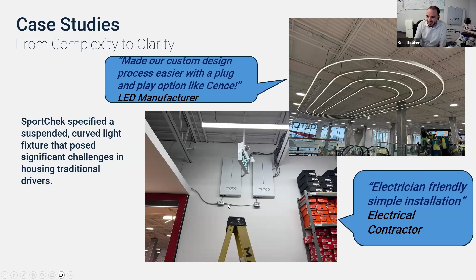Typically what they'll do is a 208 volt feed, so this will be 208 AC. In the US it's 277; in Canada we use 208, 20 amps. So they'll use one 20 amp breaker, or I guess double pole — 208 is going to be a double pole breaker to feed these.